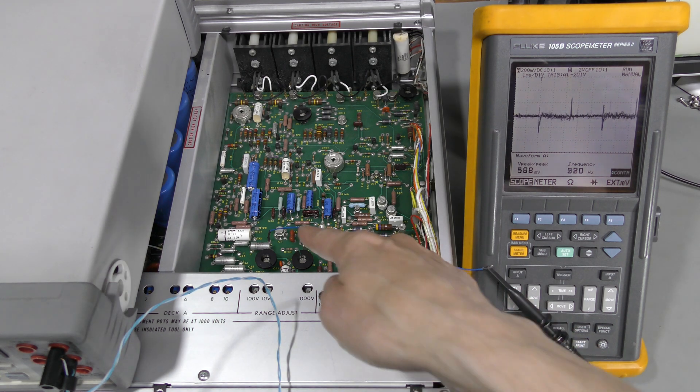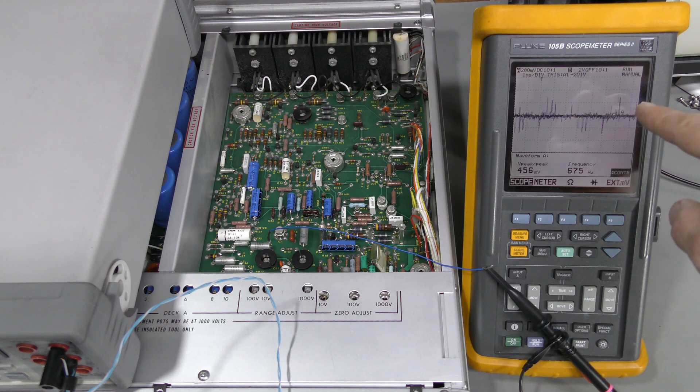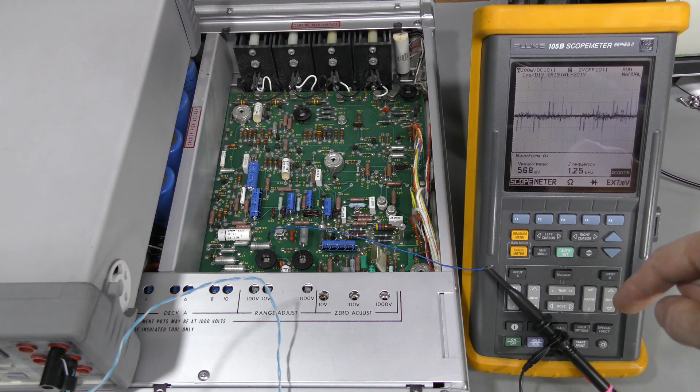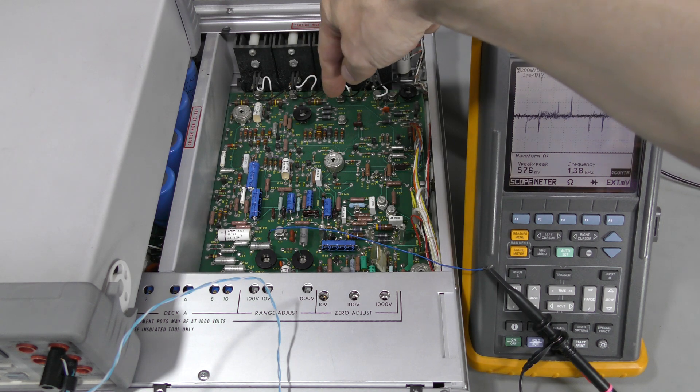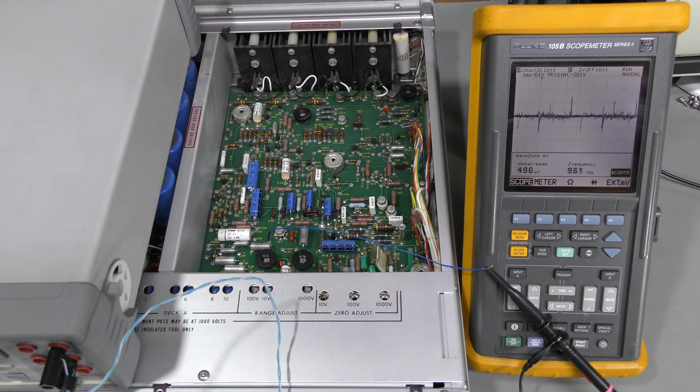There is a test point here, TP10. And we are supposed to see something like this. This is after adjustment. Spikes up and down, approximately the same amplitude and not more than 300mV or about 600mV peak-to-peak. But they were gigantic and to the negative side only. So I adjusted this pot for balance and that one for lowest amplitude. And now it looks as described in the service manual.